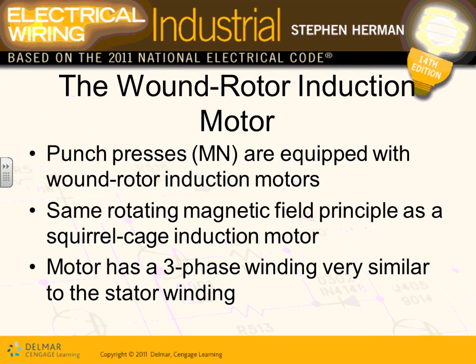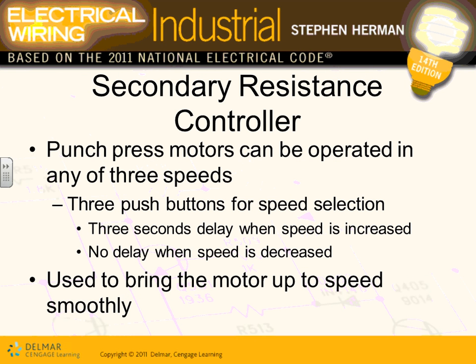Sam, how does it work? It works on the same principle, guys, as an induction motor. Except it has a secondary resistor, I'll show you. The motor can be operated in any of three speeds, so you can have full torque out of it or reduce the torque, so you can control the torque of that motor. That's the only reason why we have the windings in the secondary.